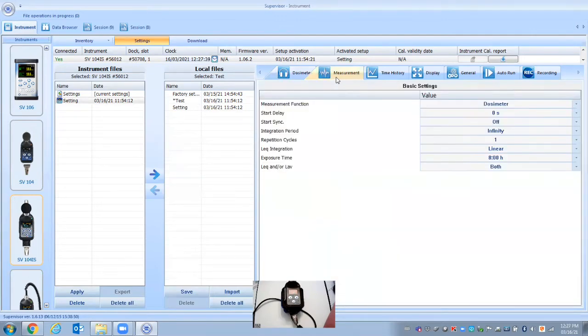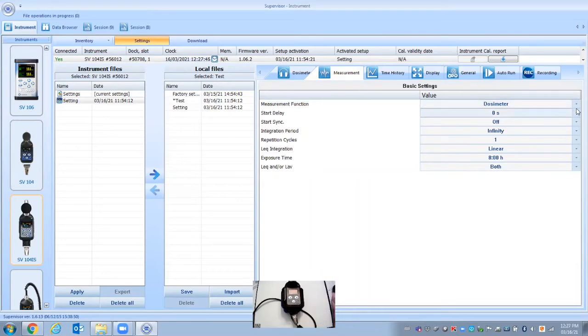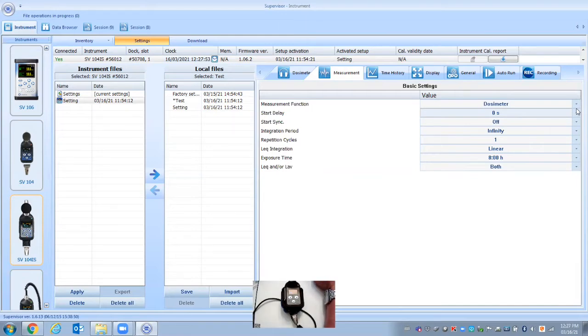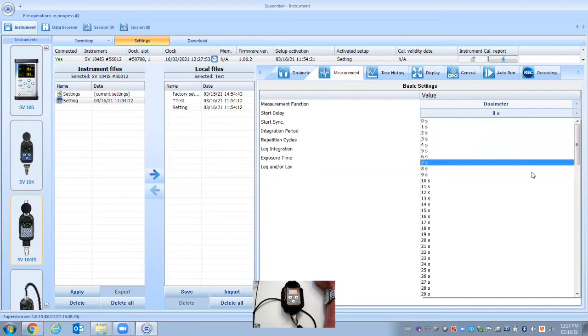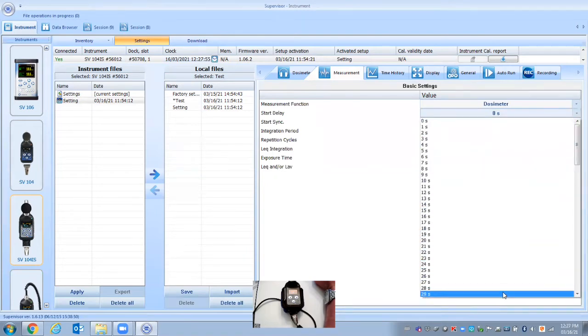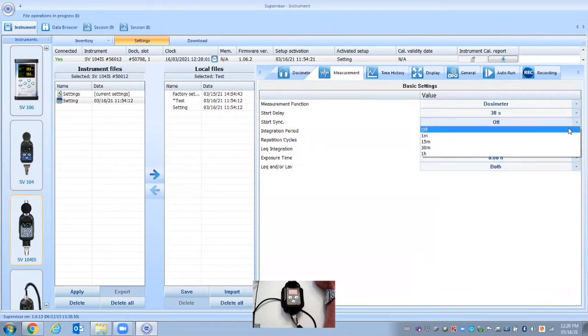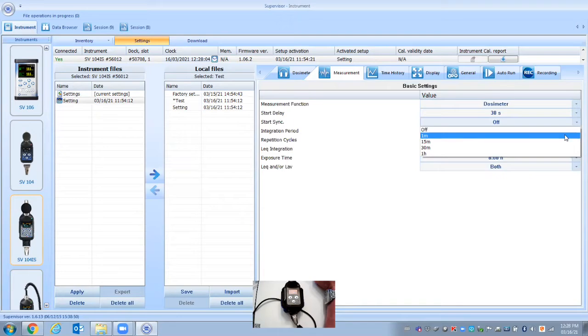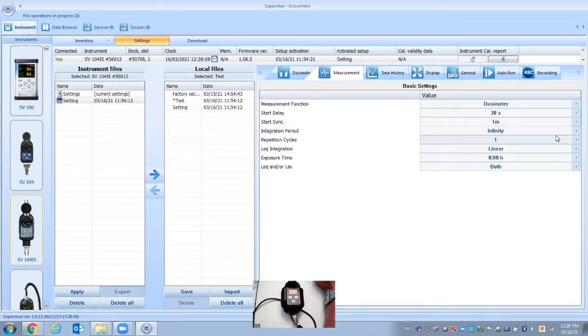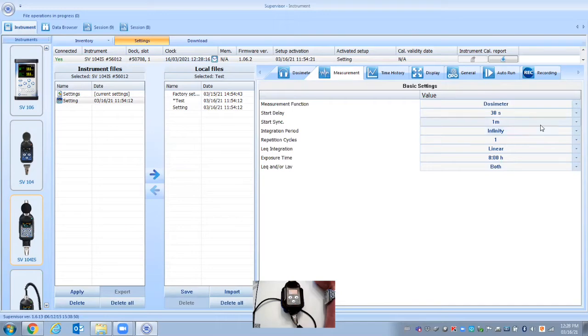Next one is our measurement. So we want to have the delay start. So if you wanted to hit start on the unit and let it sit for, I don't know, maybe 30 seconds, you could have that delay start. Synchronization is maybe if you started, it would synchronize everything to every one minute or 15 minutes so that it starts on the minute. So this is going to make your data look better if you put it to one minute integration.